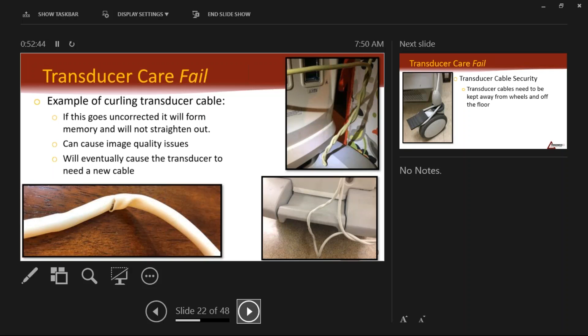Obviously, we don't want cables to be wrapped around wheels or around beds or anything else. So it's the kind of thing you just need to always be conscious of. And we talk to sonographers about this all the time. Just constant reminders: hey, remember, let's keep those cords up off the floor. Matter of fact, we go in and do PMs, and if the transducer cables are super black right where it hits the floor, it means that they're on the floor all the time. If they're on the floor all the time, they're going to get rolled over. So it's one of those things that just points out to us that, hey, we need to get the cords hung on the machines. All machines have hooks these days.